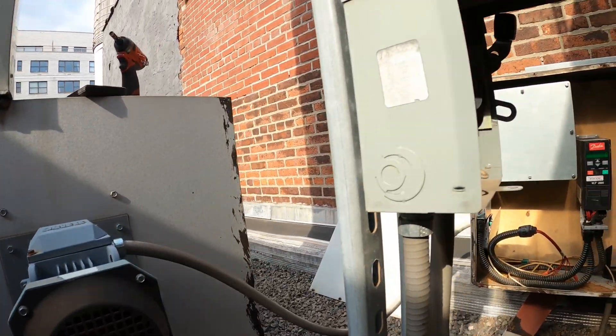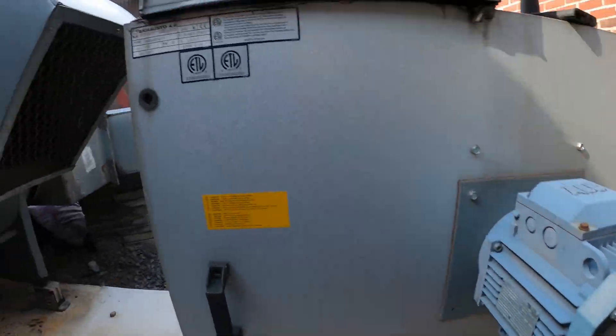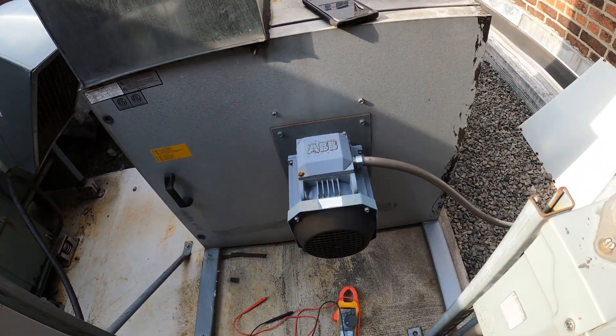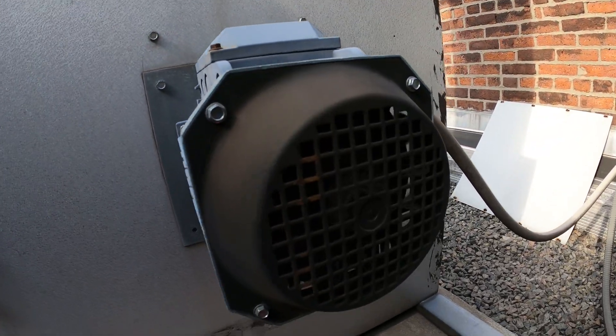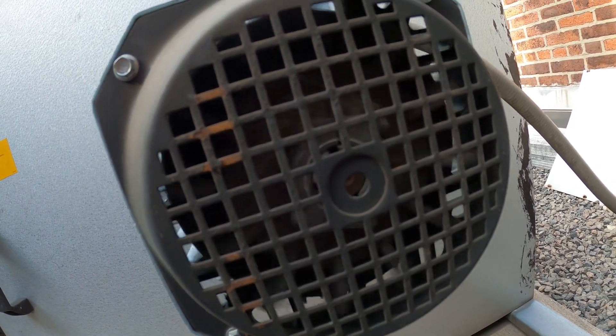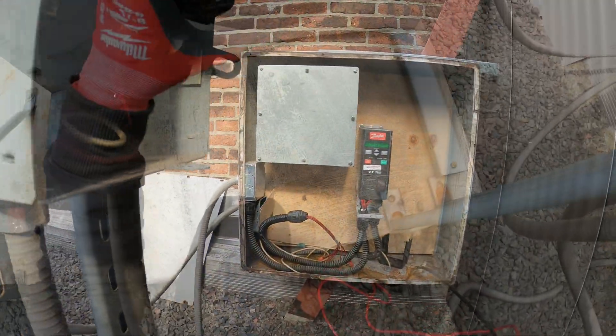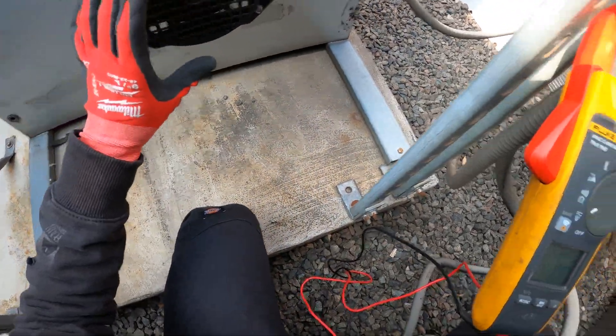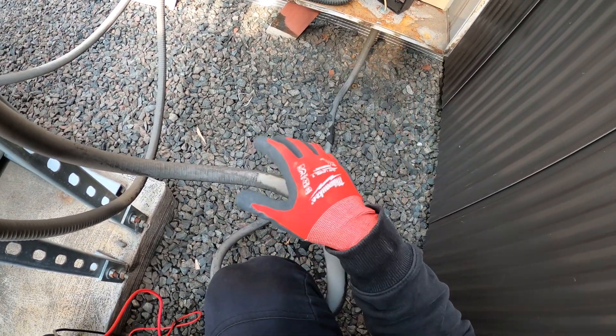This is an exhaust motor and it does work off a VFD controller. This is an exhaust for a kitchen setup and the complaint is that this is barely working. If you look at it, although you can see the shaft spinning, it's moving very slow. Let's see what's going on here. I found the issue as to why it's moving slow — it's not the VFD at all, not an issue where you would adjust the hertz or anything like that.